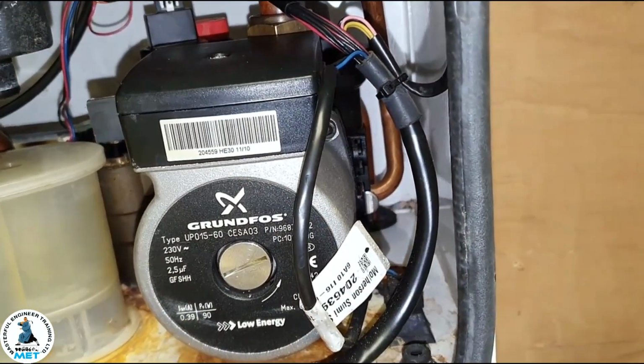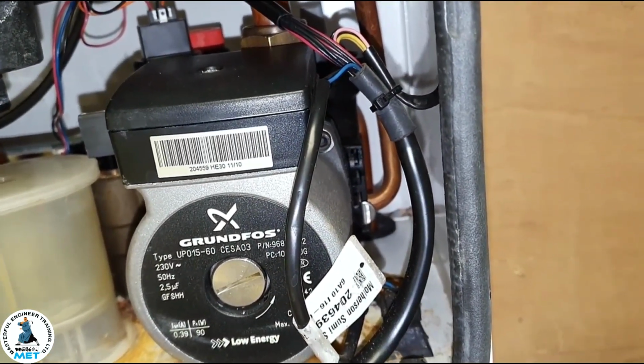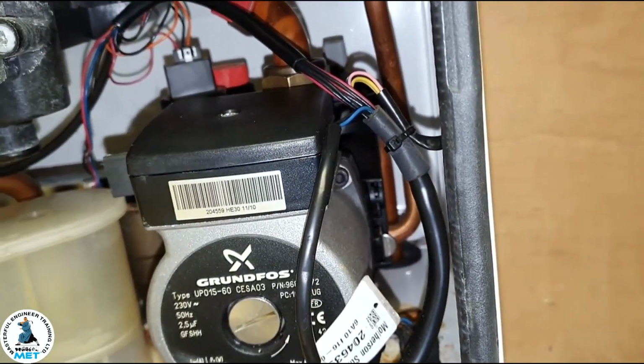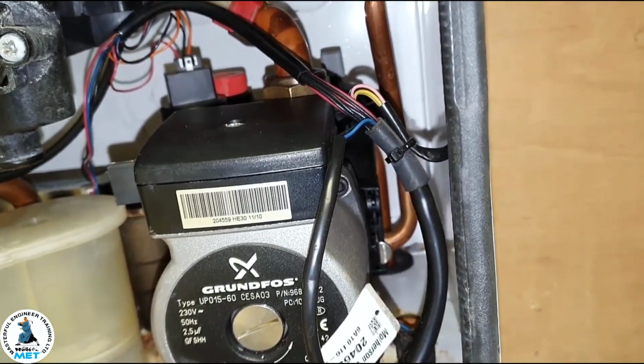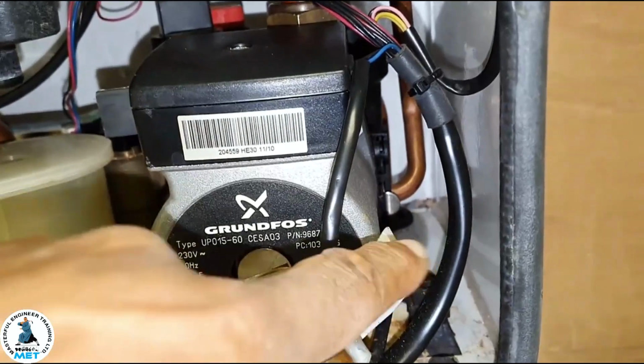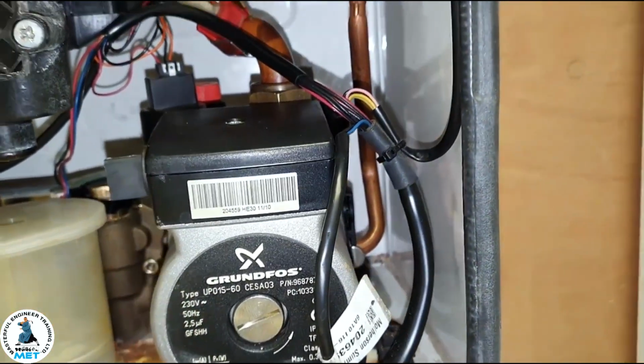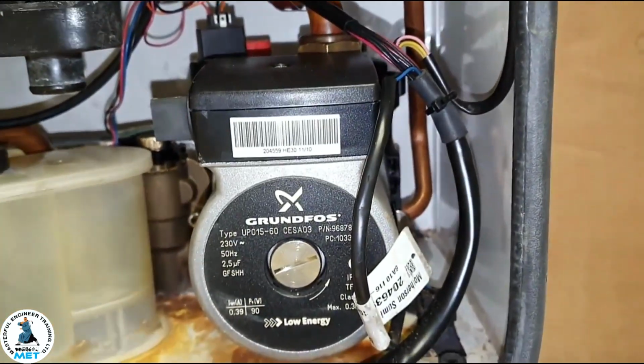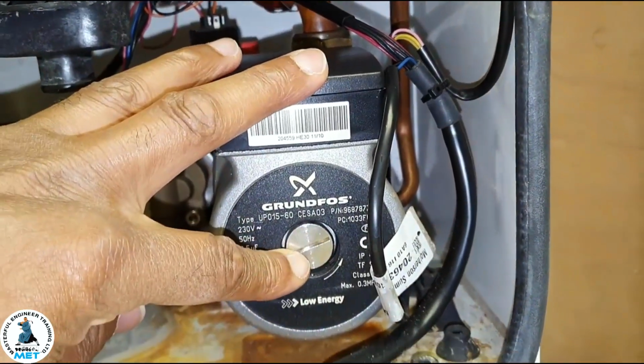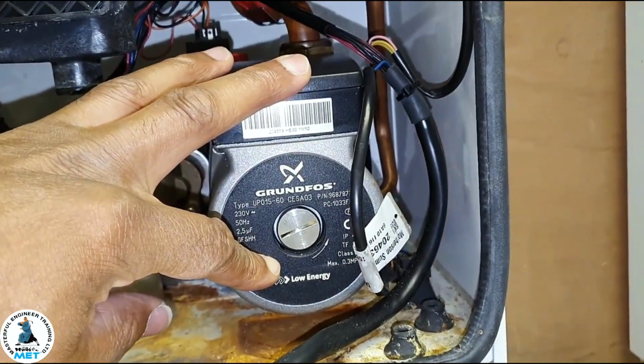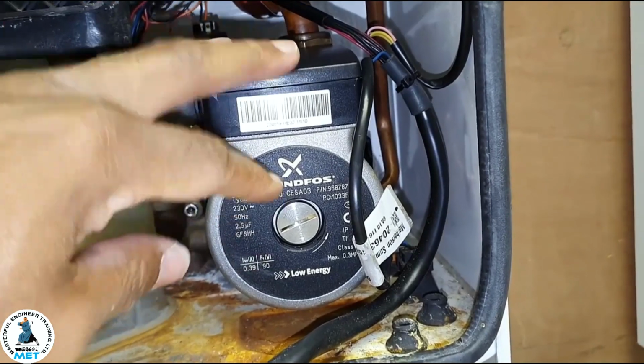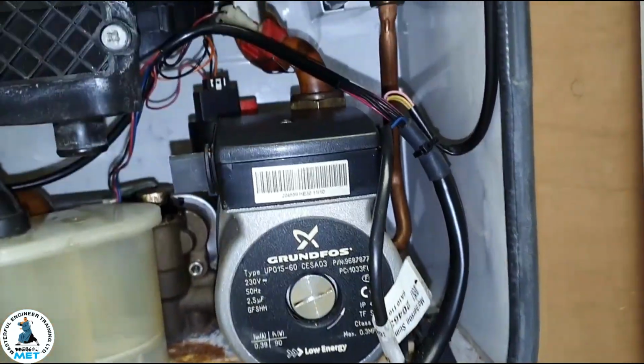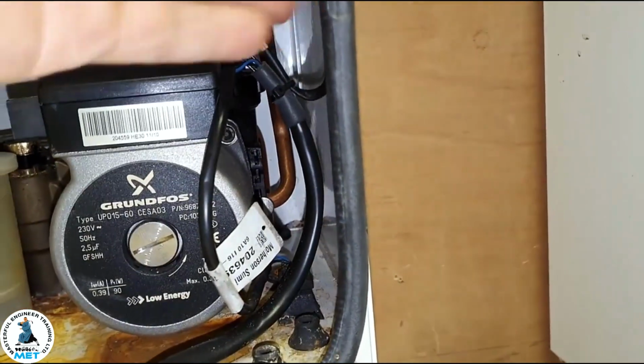Here's a great example of why I don't like this boiler. That pipe's blocked, and it's blocked right there. There's no way you're going to get in there to clear it. So if it was blocked on that bend, the pump's coming out, isn't it? You'd have to take the pump head off, which isn't a problem, however behind it's set back further, so you can't get in, you can't take the sides off on this boiler.